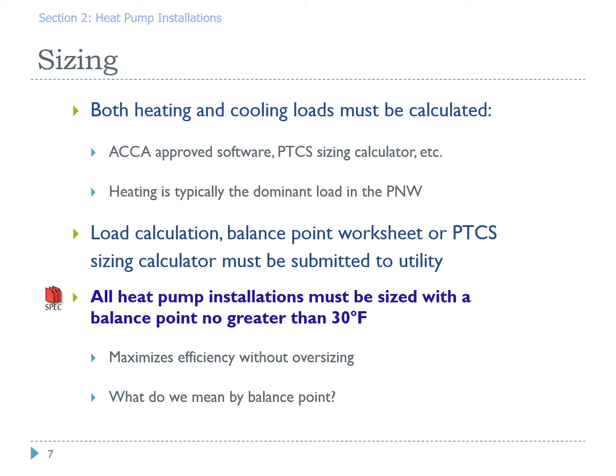Now we're going to talk about sizing. Both heating and cooling loads must be calculated. We're going to use some type of ACCA approved Manual J software or the PTCS calculator. There are a few other types of load calculation tools that could be used. And remember, heating is typically the dominant load in the Pacific Northwest. What we're going to need from you is a load calculation and a balance point worksheet. Or you could use the PTCS calculator, but these must be submitted to the utility with your paperwork.